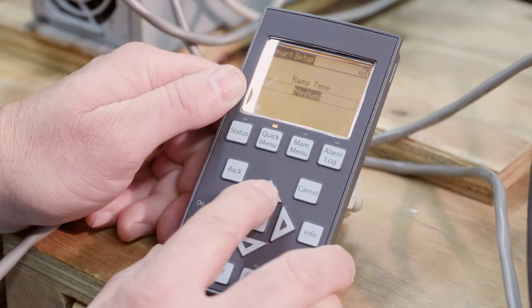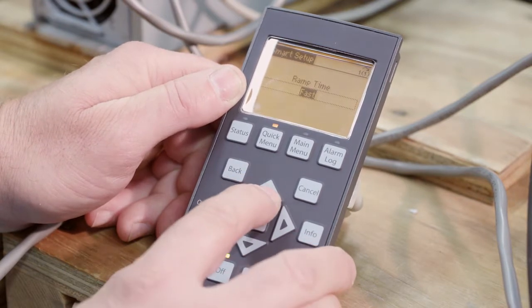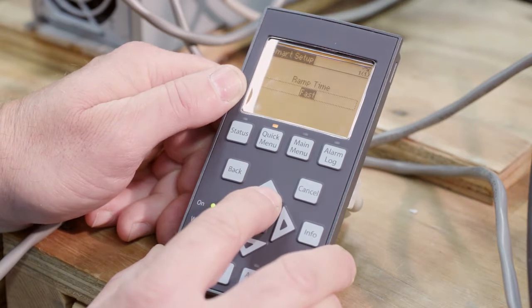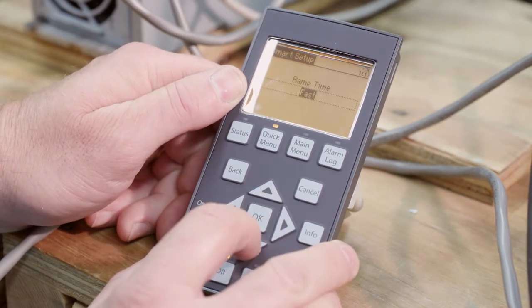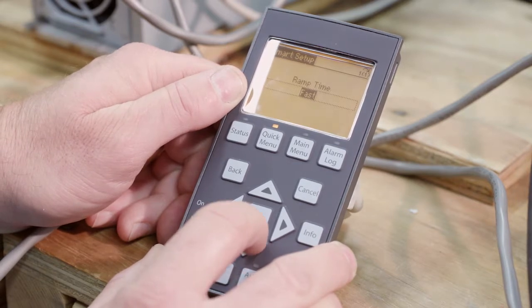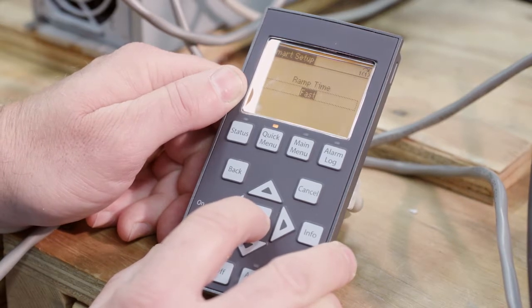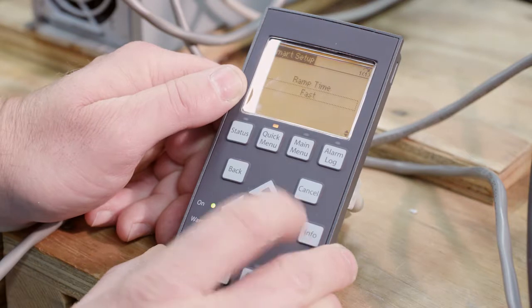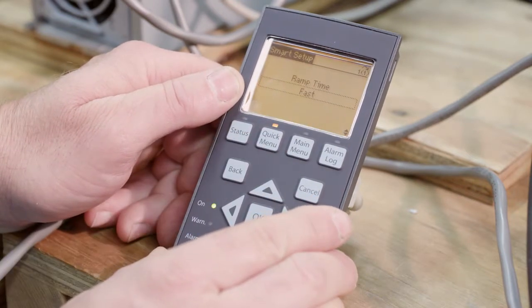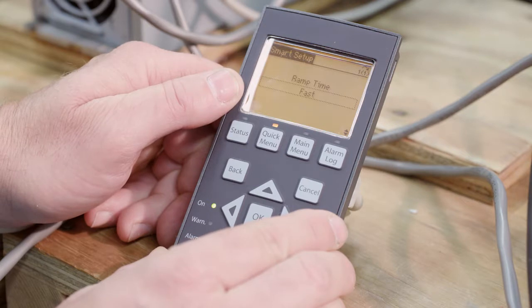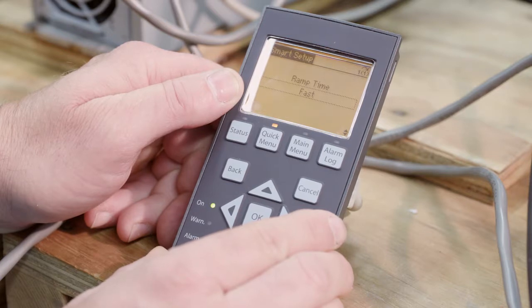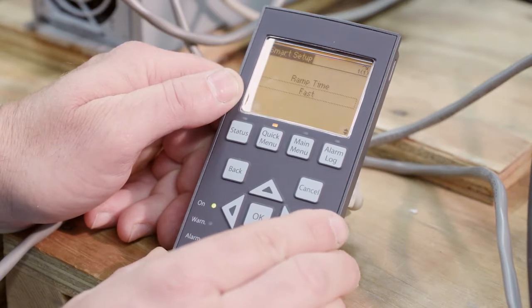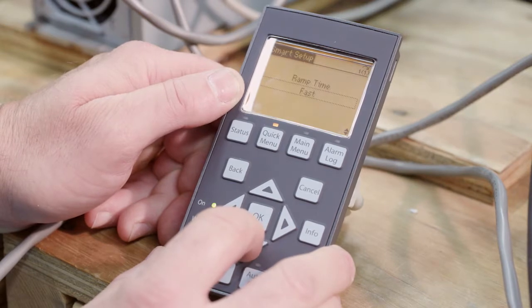So if your demand changes quickly, then you probably want a fast ramp time. If your demand doesn't change very quickly, then maybe you want slow. So in this case, we are going to be operating the discharge valve fairly quickly, so let's go with fast. Now you can make additional changes in the parameters, but again, this is just the smart setup, the Genie, and it's just designed to give us a few options to get us up and running. And more than likely, you probably will not have to get into some of those additional parameters.